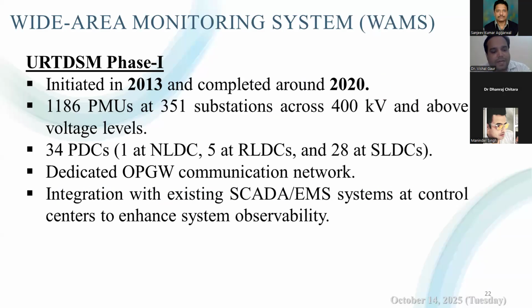About 1186 PMUs were installed at roughly 351 substations covering 400 kV and above voltage levels. 34 PDCs were deployed: one at the National Load Dispatch Center, 5 at the regional load dispatch centers, and 28 at state level dispatch centers. A dedicated optical ground wire, or OPGW, communication network was provided for reliable low latency data transfer. In this way, phase 1 integrated the synchrophasor data with the existing SCADA and EMS, energy management system. So operators could use high-speed PMU data alongside the conventional data for improved observability.